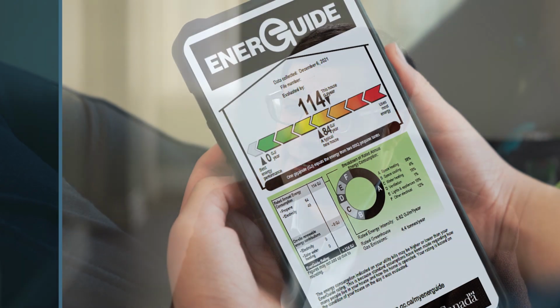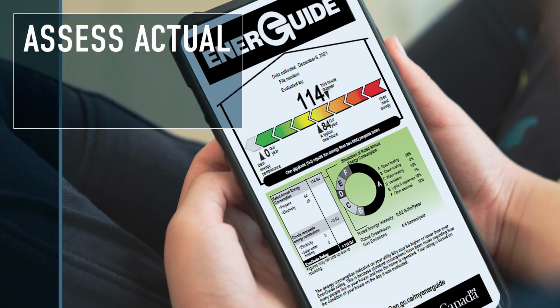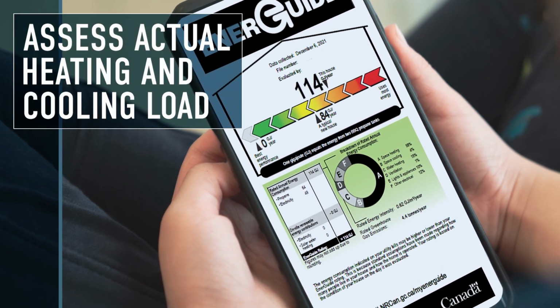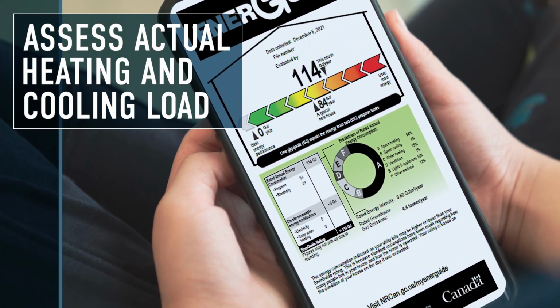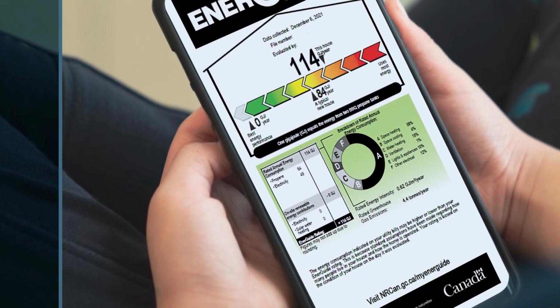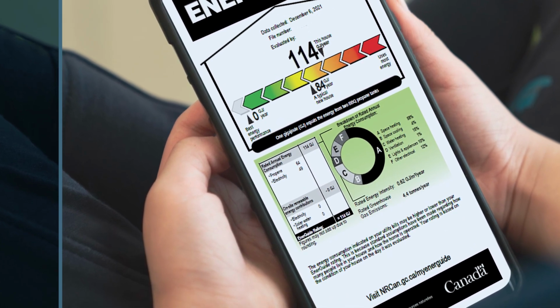The legacy furnace in this home was 72,000 BTUs per hour, or 6 heating tons. But you can't look at the existing unit and say, well, it's a 6-ton furnace, therefore it should be replaced with a 6-ton heat pump. First of all, you need to assess the actual heating and cooling loads of the home. We recommend that homeowners complete an EnerGuide Energy Efficiency Home Evaluation.